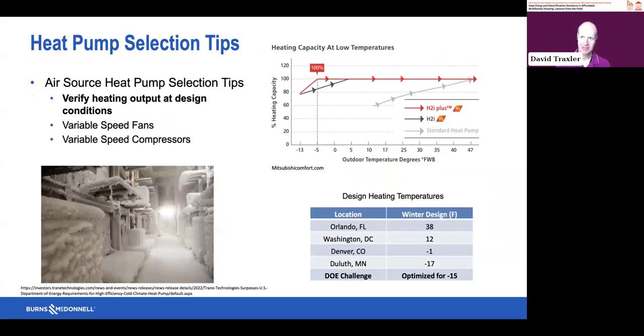On the top right is a performance graph of a heat pump, and this is really important. So if you look at the gray line, you see how the red and gray line intersect at about 47 degrees? That's because traditional heat pumps were rated for heat output at 47. It's most likely because they were originally thought to be most effective in a southern climate.